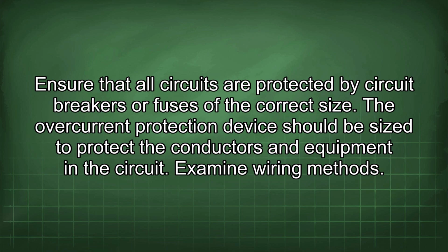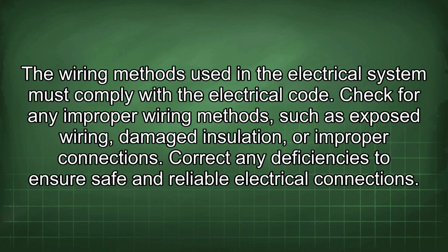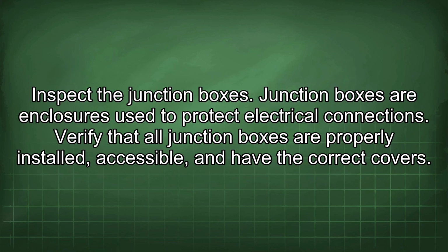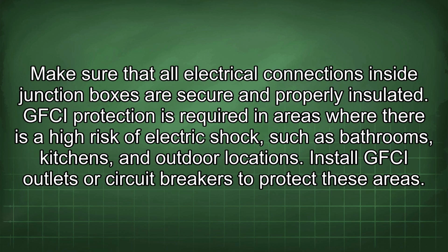Examine wiring methods. The wiring methods used in the electrical system must comply with the electrical code. Check for any improper wiring methods, such as exposed wiring, damaged insulation, or improper connections. Correct any deficiencies to ensure safe and reliable electrical connections. Inspect the junction boxes. Junction boxes are enclosures used to protect electrical connections. Verify that all junction boxes are properly installed, accessible, and have the correct covers. Make sure that all electrical connections inside junction boxes are secure and properly insulated.